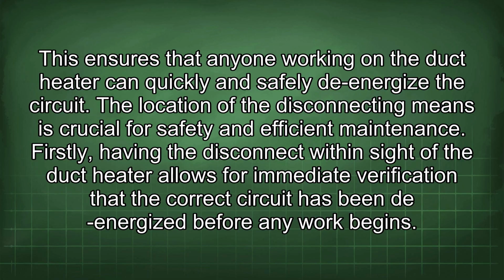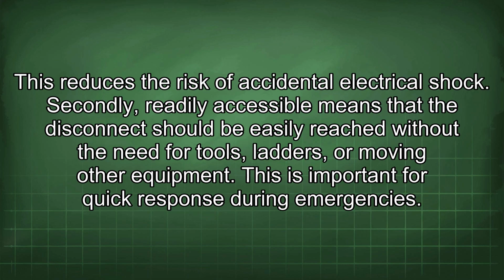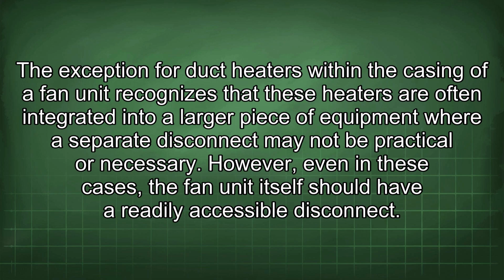Firstly, having the disconnect within sight of the duct heater allows for immediate verification that the correct circuit has been de-energized before any work begins. This reduces the risk of accidental electrical shock. Secondly, readily accessible means that the disconnect should be easily reached without the need for tools, ladders, or moving other equipment. This is important for quick response during emergencies. The exception for duct heaters within the casing of a fan unit recognizes that these heaters are often integrated into a larger piece of equipment where a separate disconnect may not be practical or necessary. However, even in these cases, the fan unit itself should have a readily accessible disconnect.